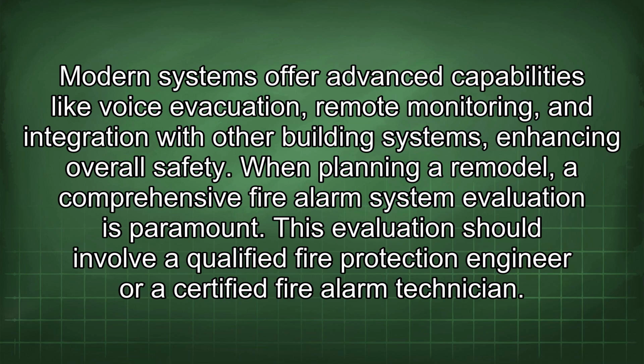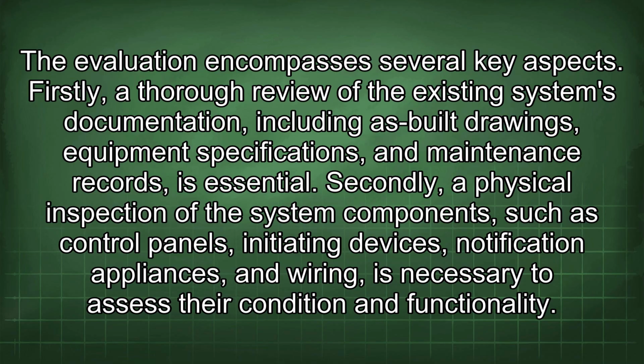When planning a remodel, a comprehensive fire alarm system evaluation is paramount. This evaluation should involve a qualified fire protection engineer or a certified fire alarm technician. The evaluation encompasses several key aspects. Firstly, a thorough review of the existing system's documentation, including as-built drawings, equipment specifications, and maintenance records, is essential. Secondly, a physical inspection of the system components such as control panels, initiating devices, notification appliances, and wiring is necessary to assess their condition and functionality.